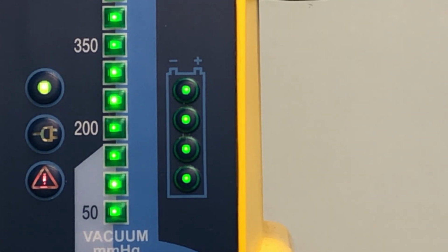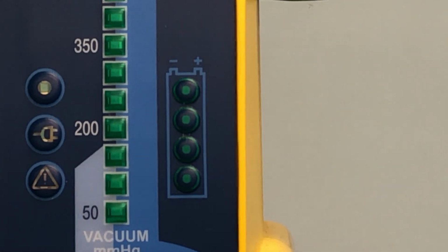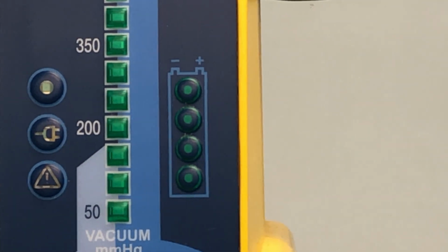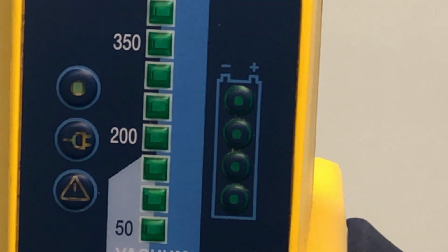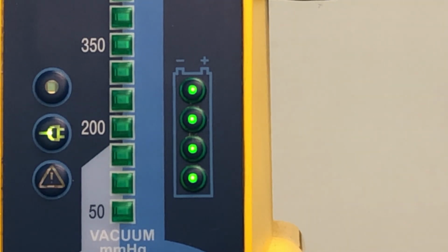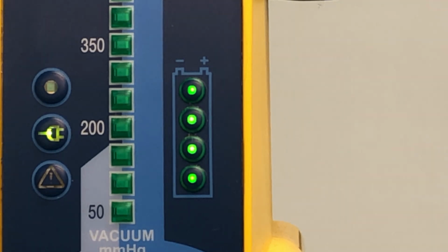During operation from the internal battery and during charging, the displayed values must only be used as indications. Several parameters can influence them, including the device settings and state of battery and temperature. The green LED bar graph has 3 functions. During operation from internal battery, it indicates the remaining battery capacity. During charging, it indicates the approximate achieved battery capacity. And during the device test, it indicates which step of the test is currently in progress or which corresponding test result is being displayed. And again, on battery, operation time is approximately 45 minutes continuous at 500 millimeters of mercury, rising to about 4 to 5 hours of intermittent operation.